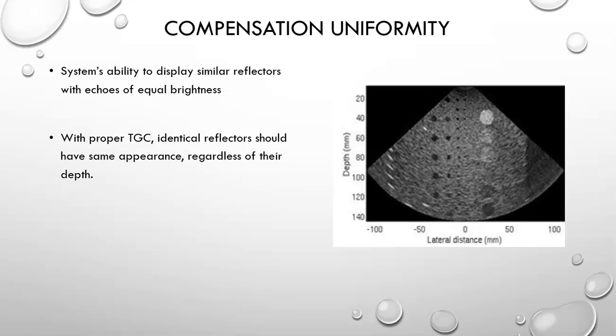Now, there's something called compensation uniformity, and this is the ability of the system to display similar reflectors with equal brightness. And so when we do this, if we set the TGCs to a certain level, then reflectors of the same material should have the same appearance regardless of their depth. So if you look at the tissue-like material in here, it looks homogeneous from top to bottom. And so we can say, yes, that looks identical from top to bottom, and so this uniformity is good on this one.